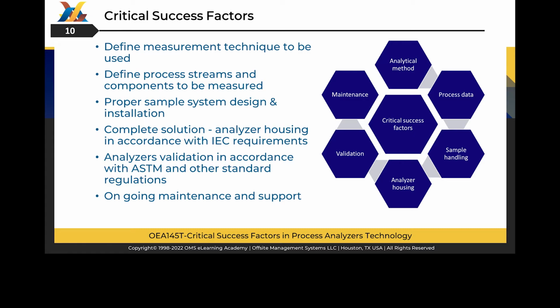Then, the complete roadmap for process analyzers project implementation should be established by considering the following critical success factors: define measurement technique to be used, define process streams and components to be measured, proper sample system design and installation, complete solution, analyzer housing per IEC requirements, analyzers validation per ASTM and other standard regulations, and ongoing maintenance and support.